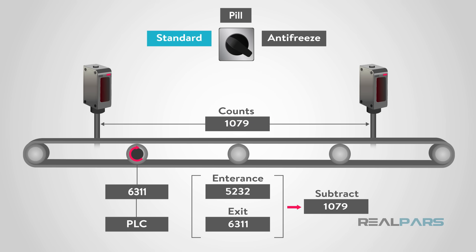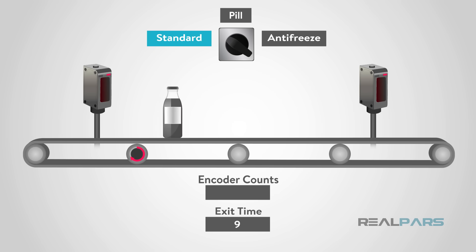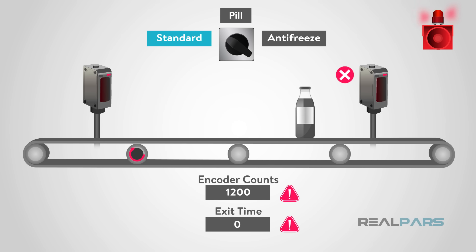That doesn't tell us that the object is 3 inches from the exit or just entering, etc. We just know that the object will enter, a count will be captured, and the object will exit, and again, the count captured. In the event that we did not see the object exiting within the allowable travel count, plus or minus a deadband, the machine will fault and the process will stop.